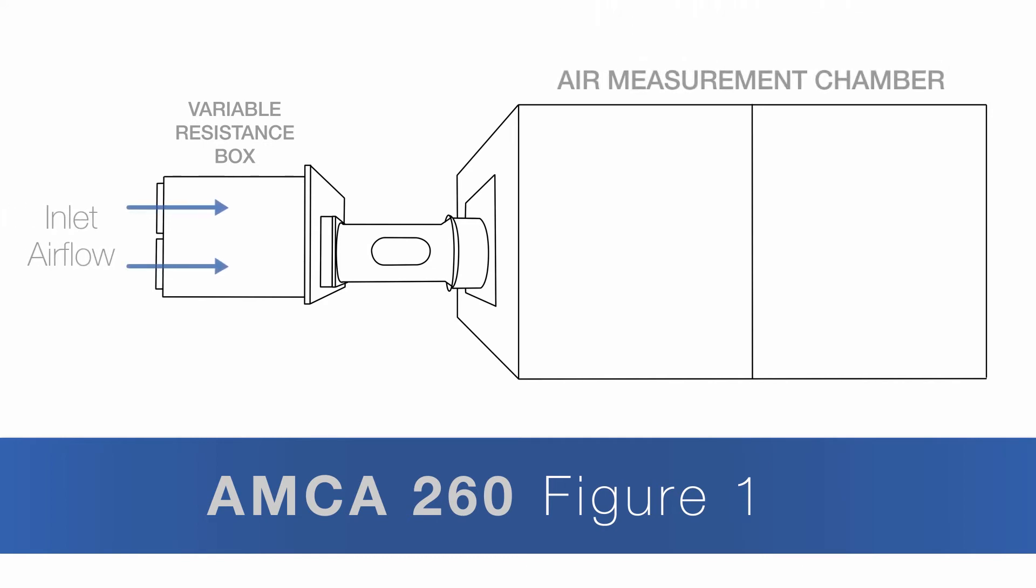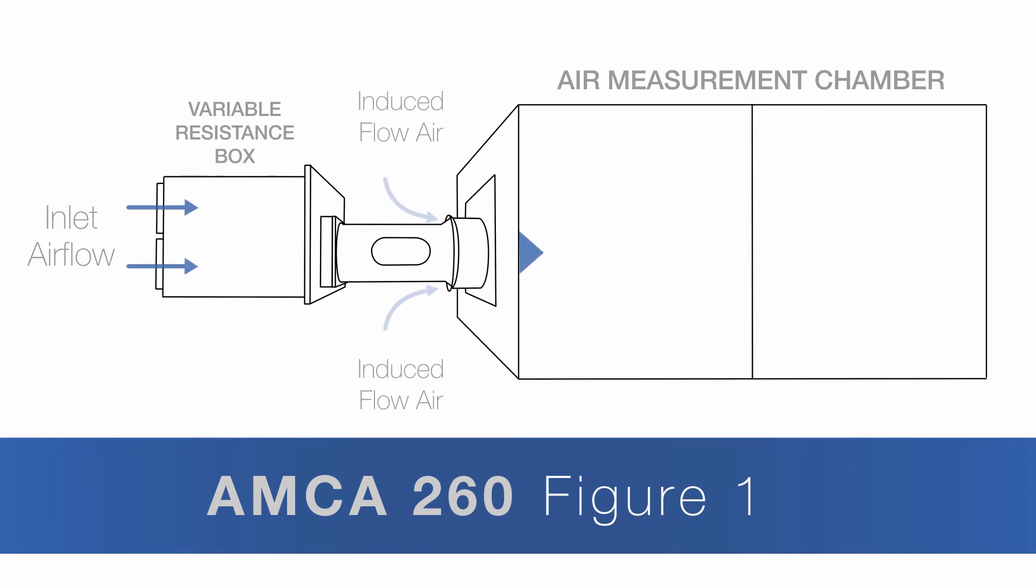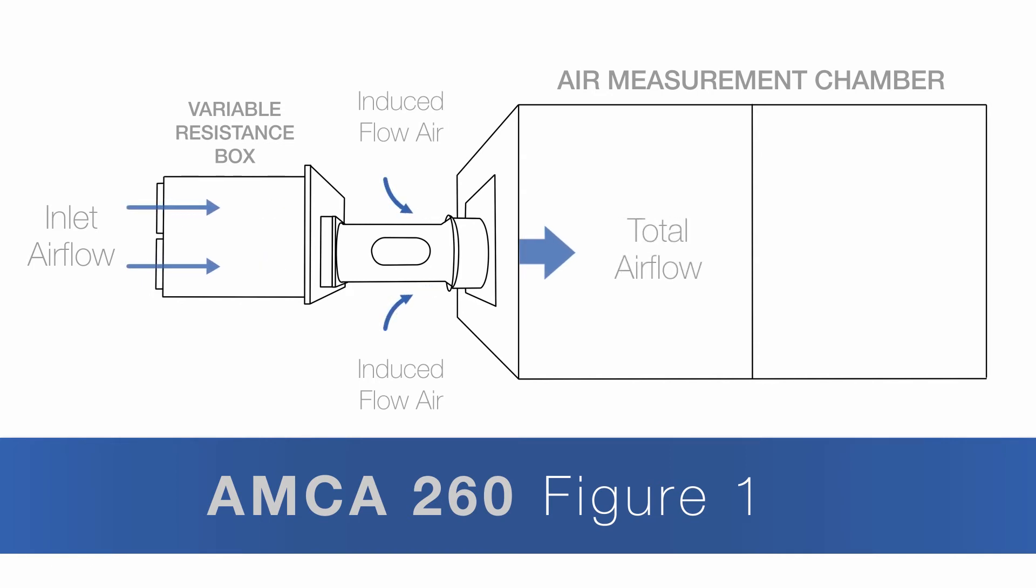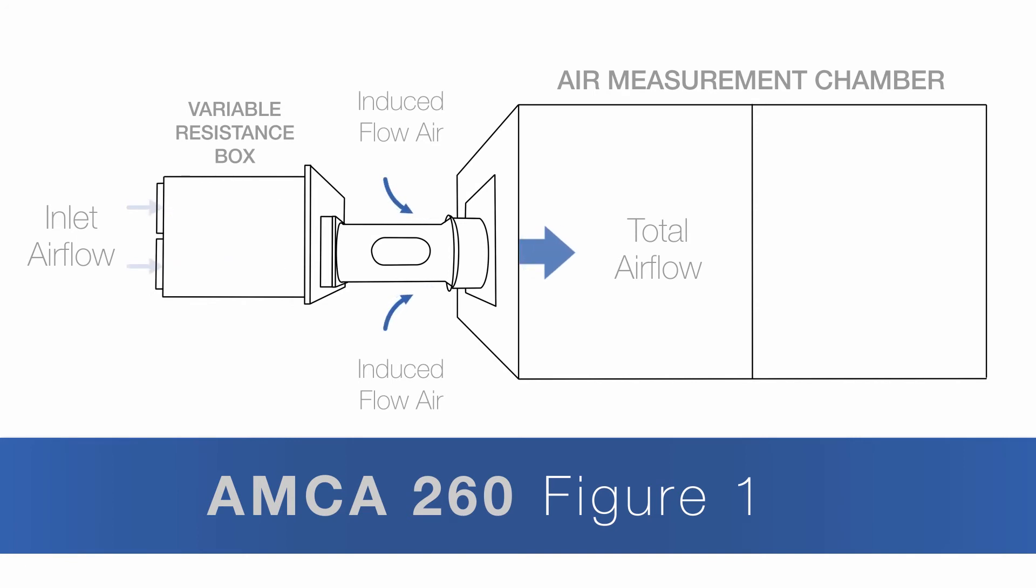With identical inlet air flows being moved by the fan in both tests, the airflow being measured in the chamber is the total airflow, both the inlet airflow through the fan and also any induced air.